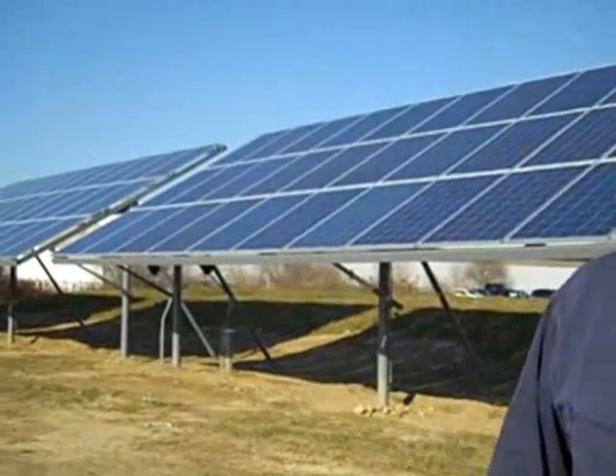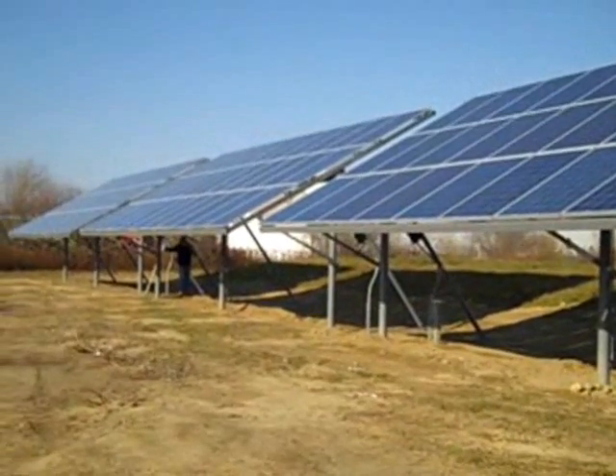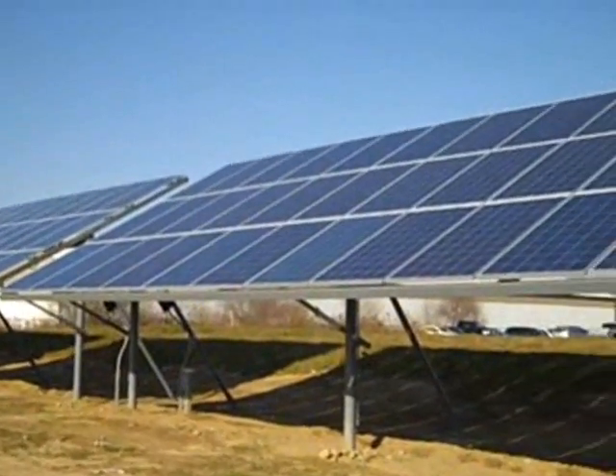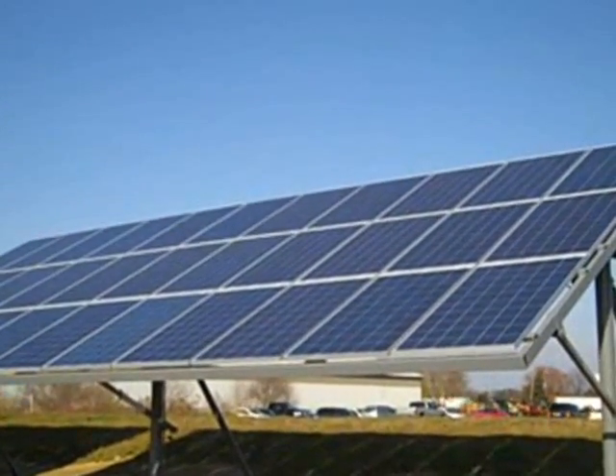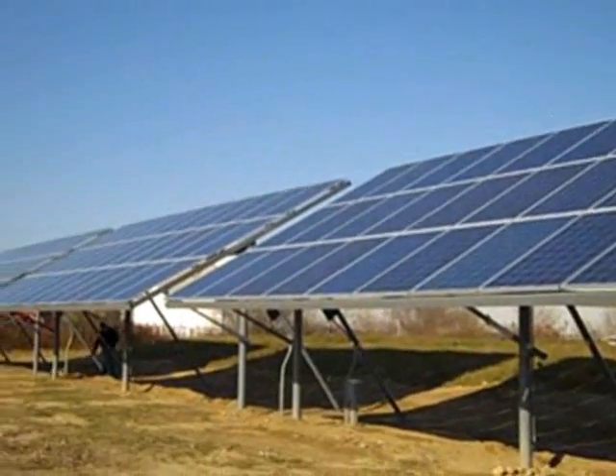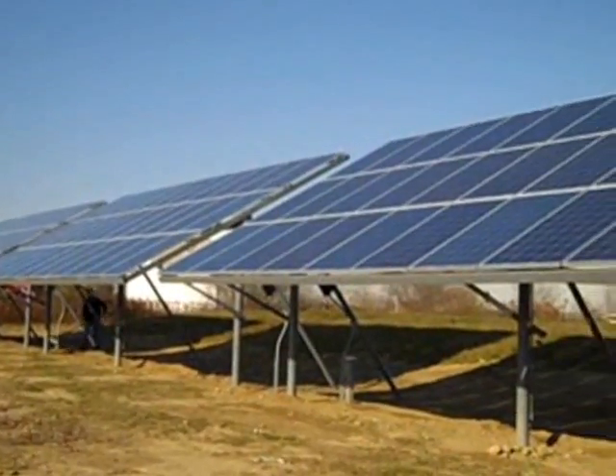We installed a 19.8 kilowatt solar system at the Tubbs Brothers dealership. And what you see behind us here is the arrays. We have 3 setups with 33 panels each, and each panel is 200 watts, and we end up with a 19.8 kilowatt system. This is fed from 3 Sunny Boy inverters that are located inside. It's a grid-tied system, and it's all connected with DTE, and it's a very productive system, and we'll show you those parts.